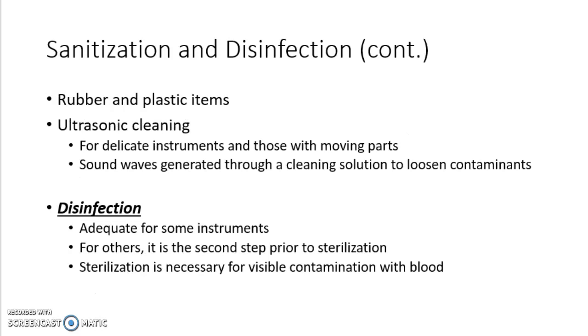There is also ultrasonic cleaning, though not all places use it — it's fairly rare. It's usually for delicate instruments or those with small hinges and moving parts, using sound waves generated through a cleaning solution to loosen contaminants. Then for the second phase — disinfection — some instruments only need to go to the disinfection stage, while for others it's the second step before full sterilization. Anytime there's visible contamination with blood or body fluids, that piece of equipment must go through the full sterilization process.